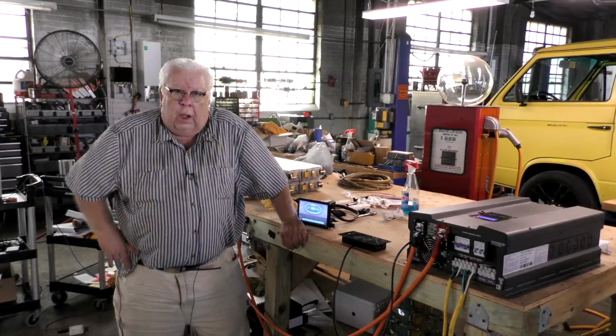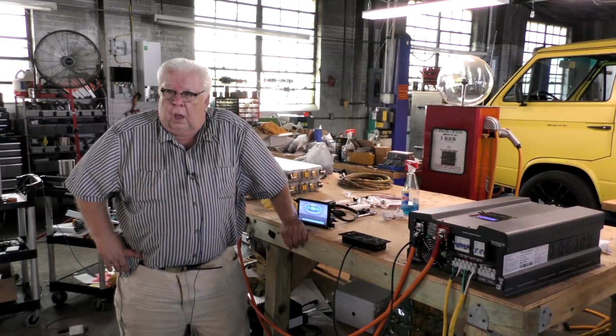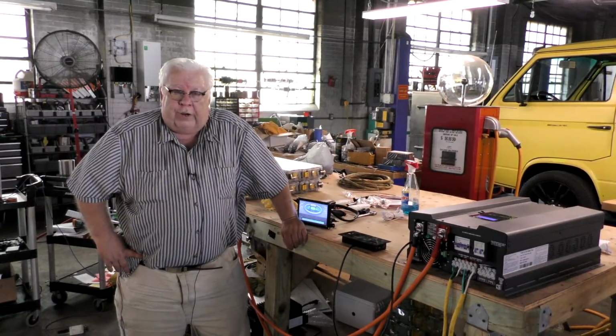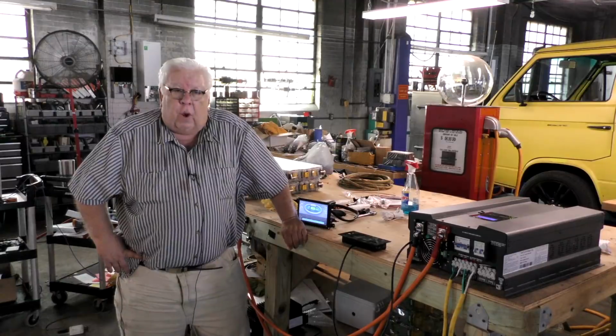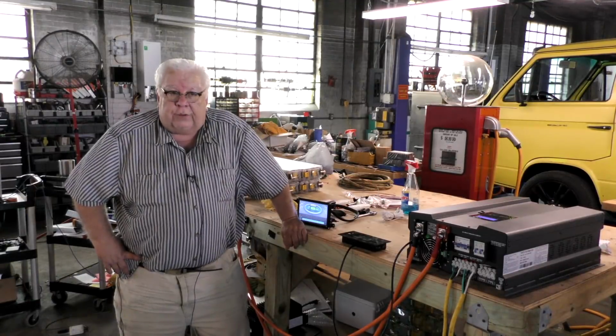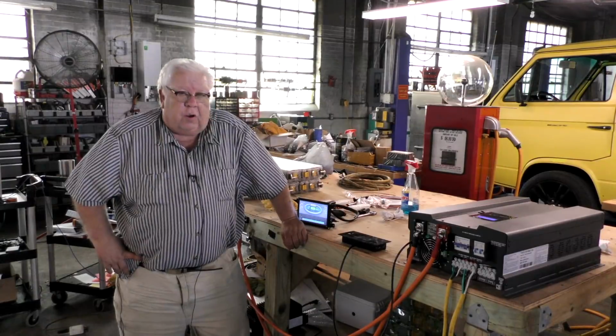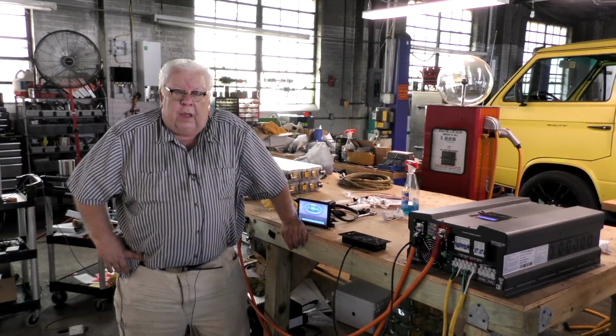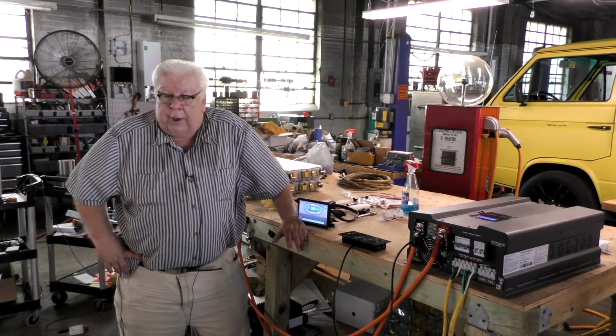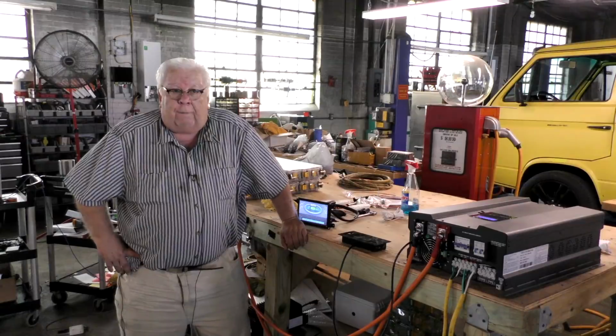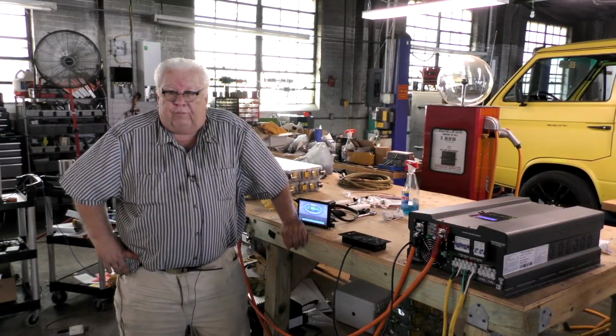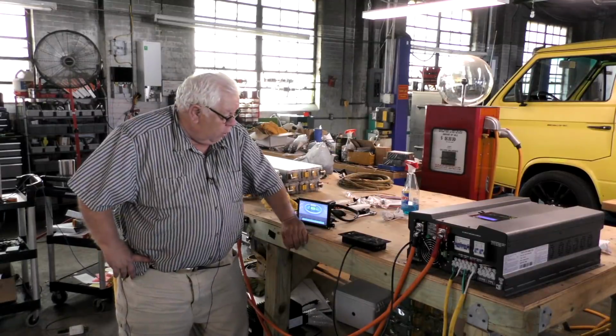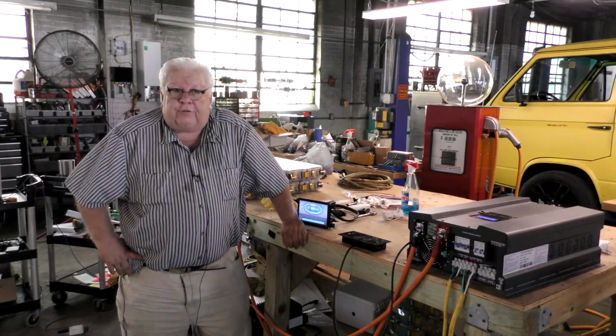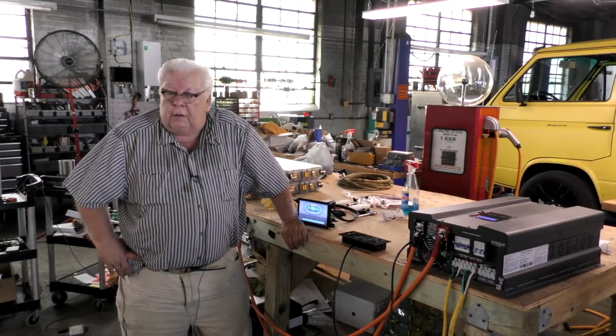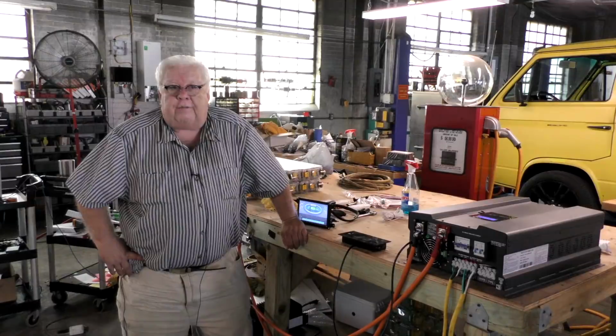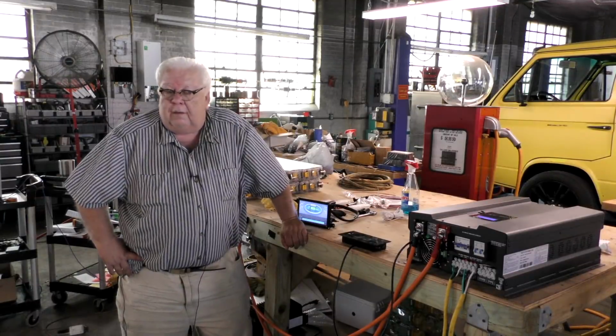But this is kind of cool because you can go to the micro inverters and bring 240 down from the roof and tie it right into your box through a contactor so we can shut it off and actually charge your batteries and feed your loads in an AC coupled fashion. And nobody knew you could do this, but it works. We're not guessing at this point. We've done it every day this week, and so far, no fatalities. So put your life alerts on stun and cinch up your depends, old guys. We're going in. Stay with us.